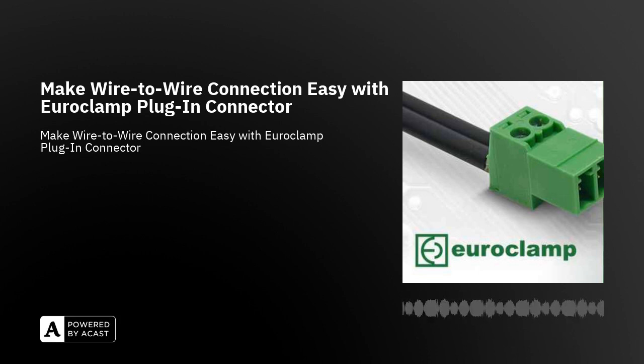Features and advantages of the SFXX381P series of terminal blocks from Euroclamp. Number of pins, 2 to 24. Operating temperature range from -40 to +130 degrees Celsius. Maximum current, 11 amps. Maximum voltage, 200 volts. Conductor cross-sections, 0.2 to 2.5 square millimeters.